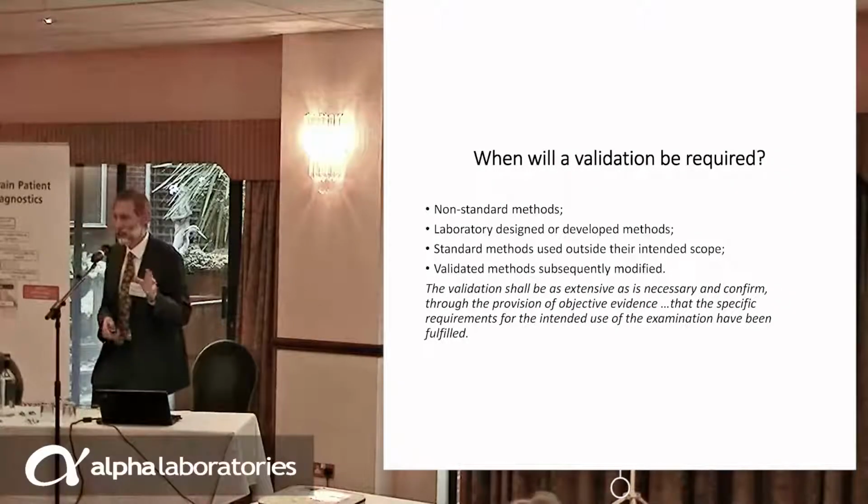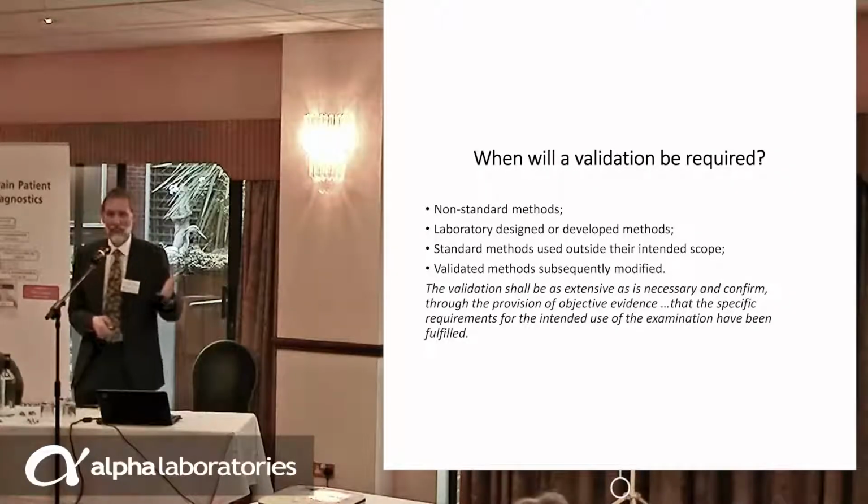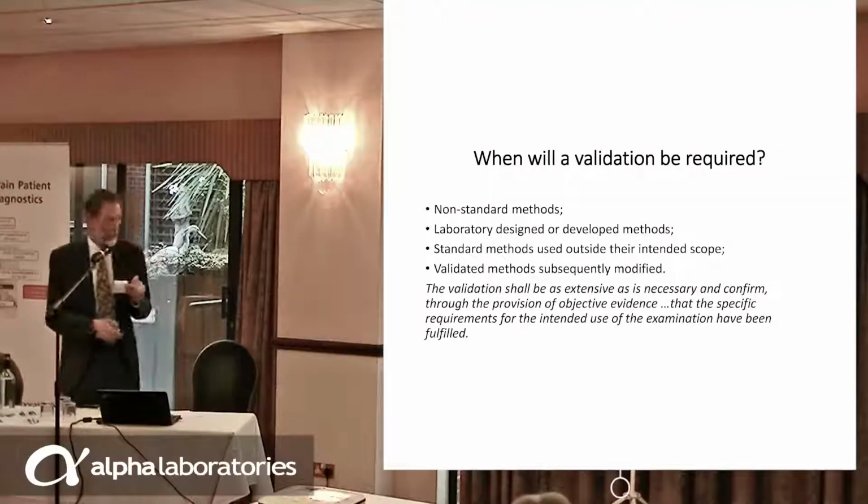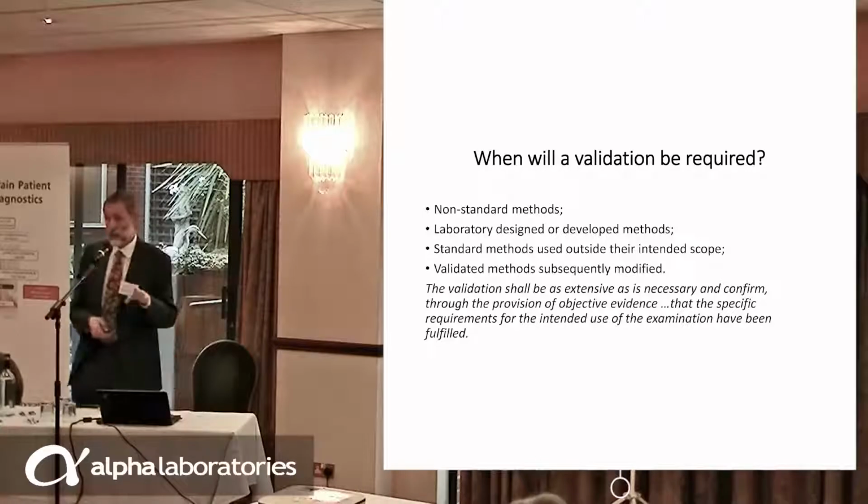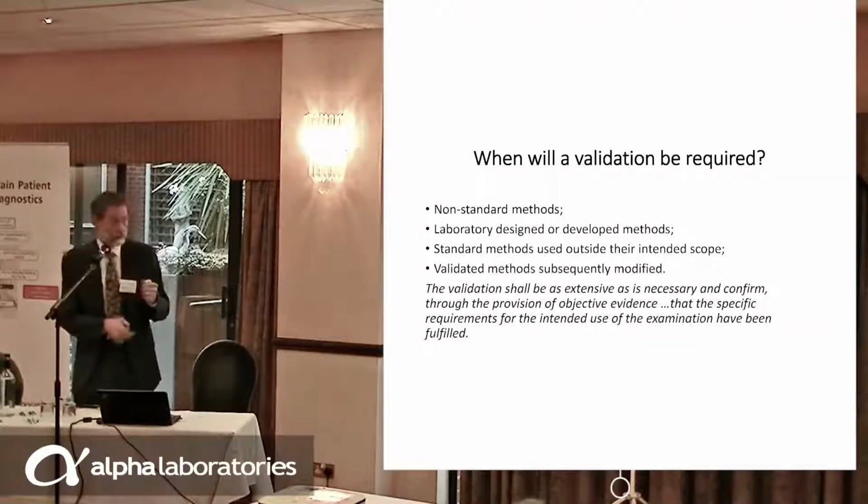Fluids, okay? So who runs pleural fluids through their main analyzers, okay? We do it, don't we? You will not find any manufacturer who will make any claims about fluids. Okay, so I think in that situation you needed to do some validation work, okay? Now I think pleural fluids behave very, very similarly to serum or plasma, but providing evidence of that is actually something I think if you want to get it in your scope, you're going to have to do.